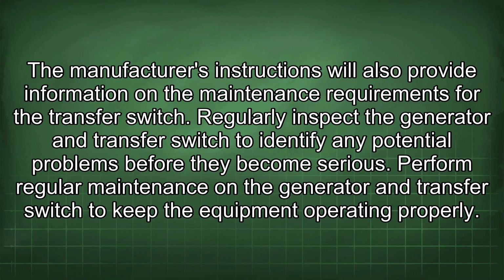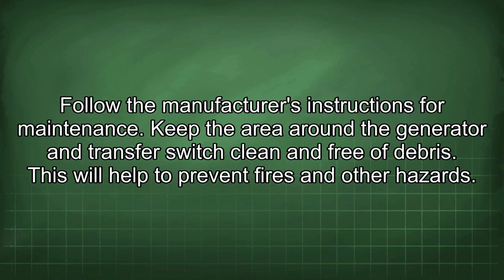Regularly inspect the generator and transfer switch to identify any potential problems before they become serious. Perform regular maintenance on the generator and transfer switch to keep the equipment operating properly. Follow the manufacturer's instructions for maintenance. Keep the area around the generator and transfer switch clean and free of debris. This will help to prevent fires and other hazards.